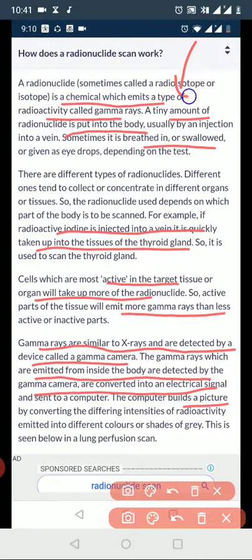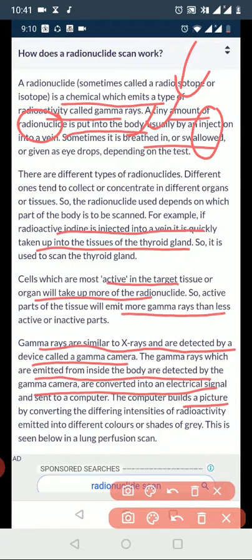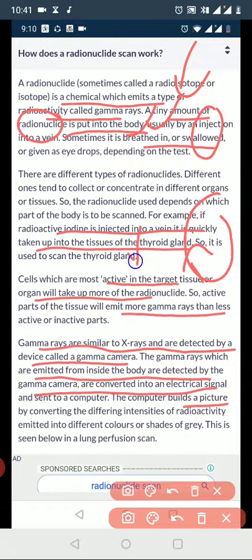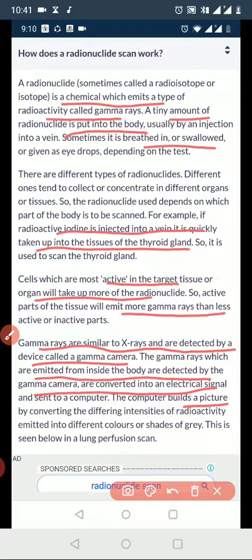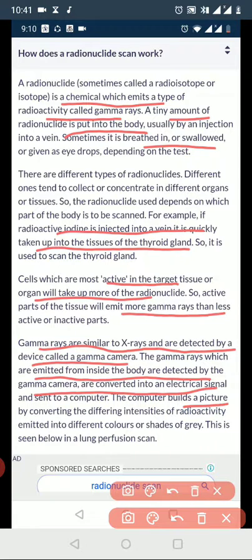A radionuclide scan uses a chemical that emits gamma rays. A tiny amount of radioactive material is introduced into the body — usually injected into a vein — where it is quickly taken up by active cells. Cells that are most metabolically active take up more of the radiotracer and emit more gamma rays. These gamma rays, similar to X-rays, are detected by the gamma camera, which converts them into electrical signals processed by a computer.